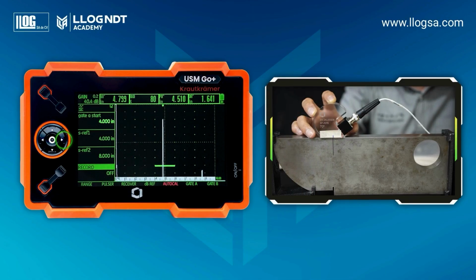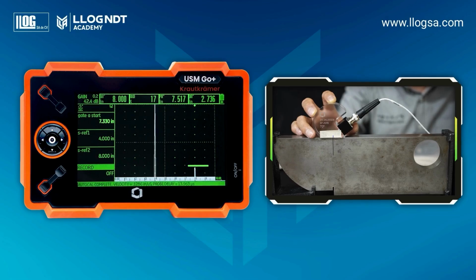In the record function, press the right navigation key once to activate the auto-calibration function. Save the first reference by pressing the right key again. Next, move the gate to the second echo. Increase the decibels slightly so that the indication amplitude touches the gate. To save the second reference, press the right key once more. Finally, verify that the distances are correct. 8 inches and 4 inches.